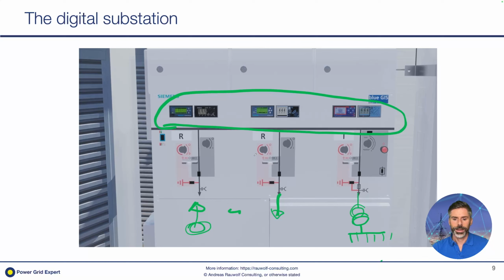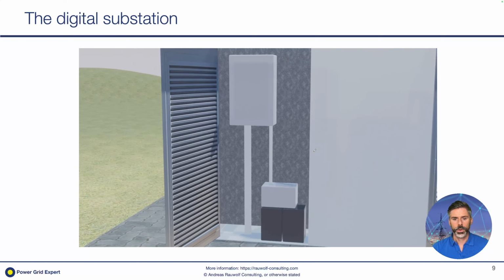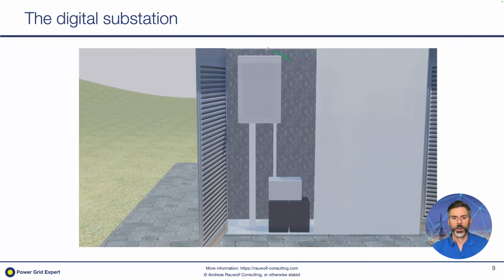The voltage information comes out of the capacitive indicators here, or it comes from so-called ohmic sensors. We will see them later when we have a look at the transformer. So we're continuing to the RTU compartment, and here we have a box that normally contains the RTU unit, the remote terminal unit. Additionally, a modem which connects the whole system to the SCADA. That can be some wireless technology, that can be 5G, that can be fiber, of course, that can be copper lines, that can be satellite. There's lots of different technologies available depending on what's the best in this situation.